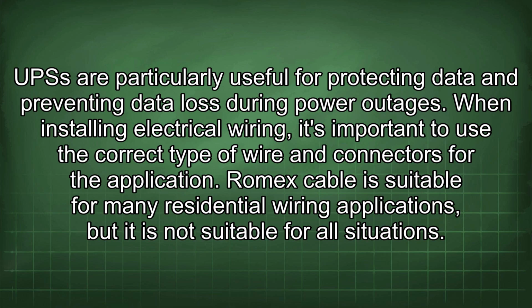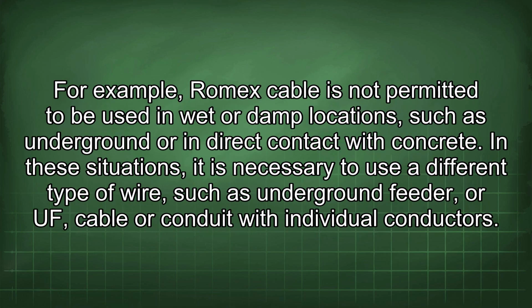Romex cable is suitable for many residential wiring applications, but it is not suitable for all situations. For example, Romex cable is not permitted to be used in wet or damp locations such as underground or in direct contact with concrete. In these situations, it is necessary to use a different type of wire, such as underground feeder, or UF, cable or conduit with individual conductors.